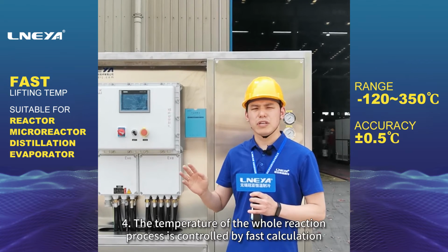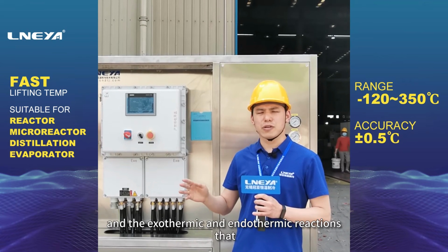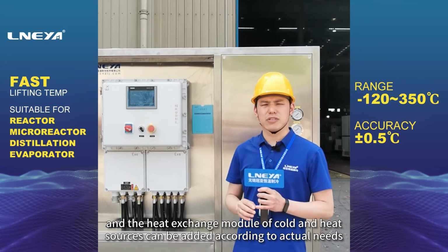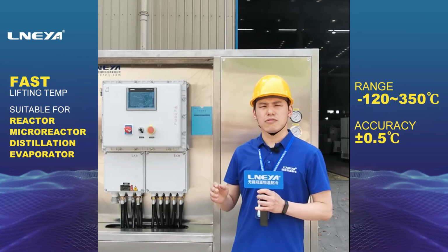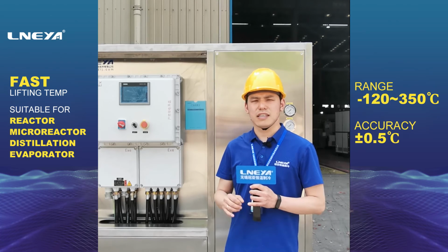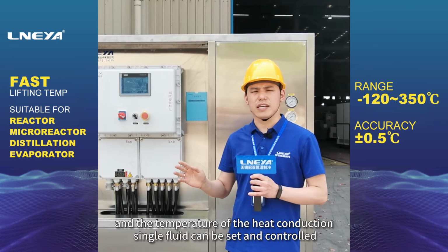Fourth, the temperature of the whole reaction process is controlled by fast calculation, and the exothermic and endothermic reactions that occur in the whole reaction process are quickly controlled. A standardized interface is reserved, and the heat exchange module of cold and heat sources can be added according to actual needs. Fifth, the temperature of the reaction process and the temperature of the single fluid can be optionally controlled, and the temperature difference between the temperature of the reaction process and the temperature of the heat conduction single fluid can be set and controlled.